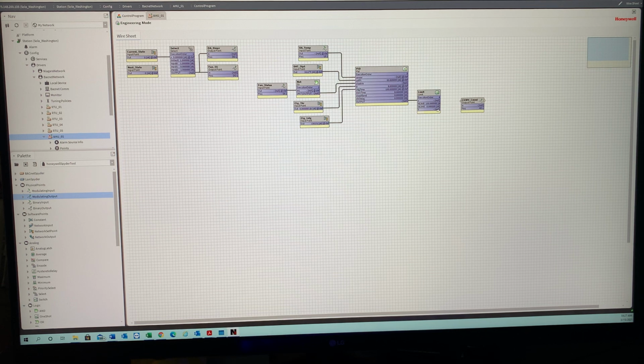It could be 0 to 5. We've done a lot of water plants where there are different types of actuators, meters, and back flushes that use different voltages, where this all comes in super handy. Here's our advanced. If we need to change any of this, which for this we do not. So we have our 2 to 10 set up. Then we go here. Like I said, this is just the real basic. Let's get started. Here's a chill water valve command.